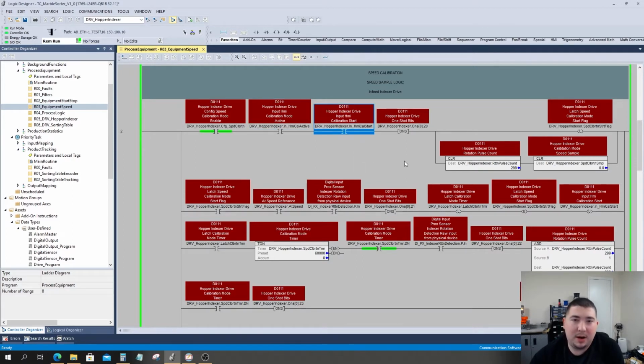But we don't want to automatically start monitoring our feedback as soon as the drive comes on. If you think about it, we are still going to have to ramp the speed up to our actual set speed. And until we've reached our set speed, we don't want to start monitoring anything. So the first thing we do is latch this flag bit. In addition, we go ahead and clear any current values that are stored in the system from our last calibration sequence. That way they don't interfere with our current values. The set bit is turned on, this will actually command the motor to start, and we've already given it the speed that we want to run at, so it will begin accelerating.